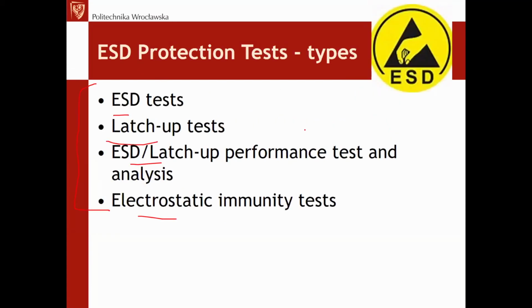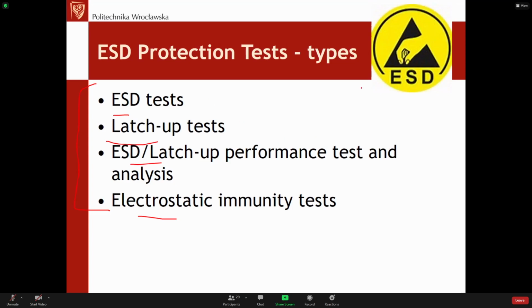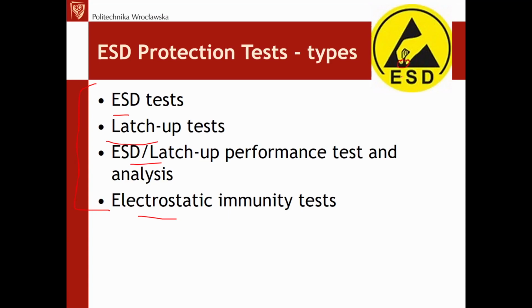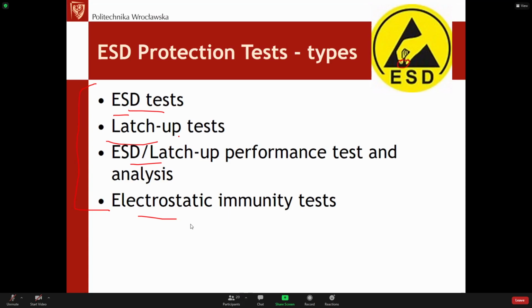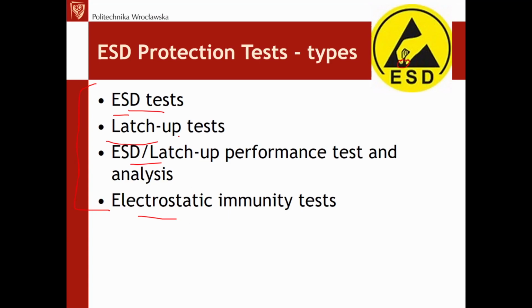Because, by the way, the simplest way of testing the ESD is the simulation of a human being. Of course, nobody will use a human being and charge and discharge a human being, but there are special guns. There are special guns that charge to a few kilovolts, and the simplest test for ESD protection is to shoot with this gun at our device, at various parts of our device, like connectors, like displays, like the case. During the test, the operator shoots at the device with a single pulse or a pulse train of a few kilovolts, and if the device survives, then it's protected as well. It's properly designed against the ESD.